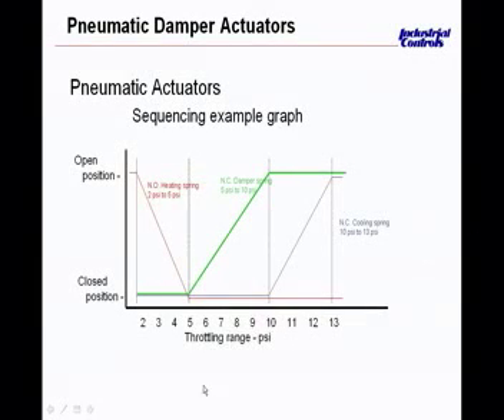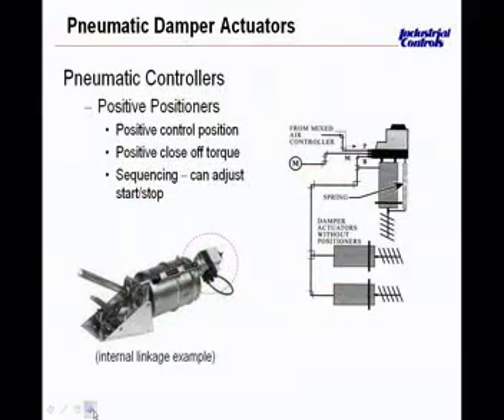So now we get into positioners. We talked before about valve actuator positioners, positive positioners, and we also have the equivalent of those for the damper actuators. So we take a look at the slide and follow the cursor here, that on the side of this particular model, we have a rod and spring that's attached directly to the stem as it extends out of this damper actuator. So this is physically giving some feedback of where this is extending out or not extending out. It's actually giving feedback directly into this positive positioner.